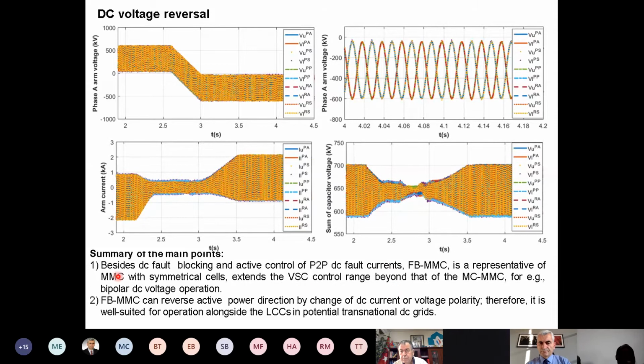We can say beside DC fault blocking and active control of pole-to-pole DC fault, the full bridge is a representative of the MMC with symmetrical cells, which extends the VSC control range beyond that of the mixed cells MMC. For example, as we just showed here, bipolar DC voltage operation. And the second point is that the full bridge can reverse active power direction by change of DC voltage polarity. Therefore, it is well suited for operation alongside the LCC in a potential transnational DC grid.